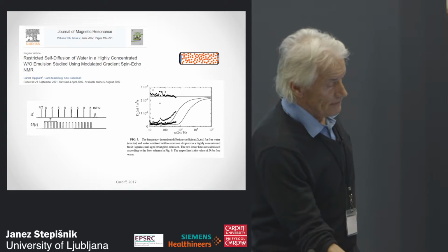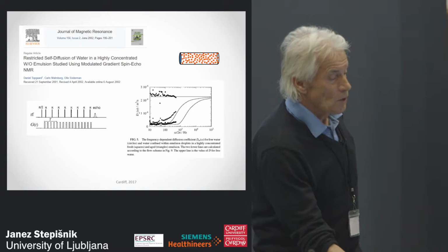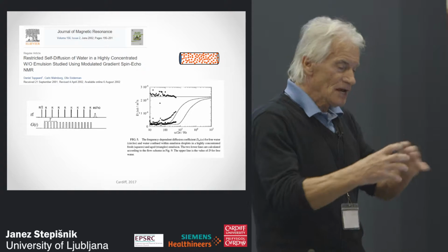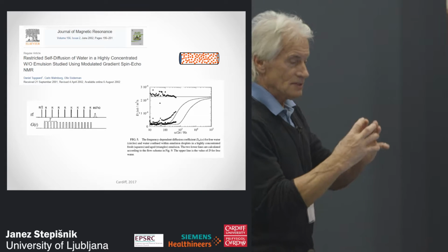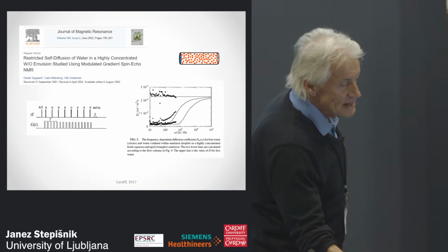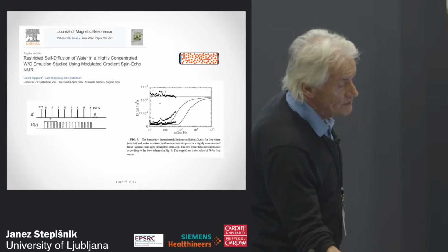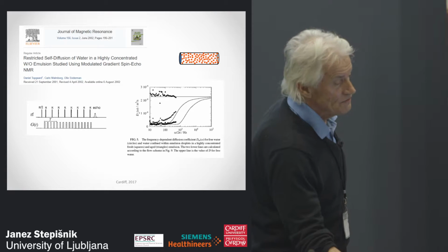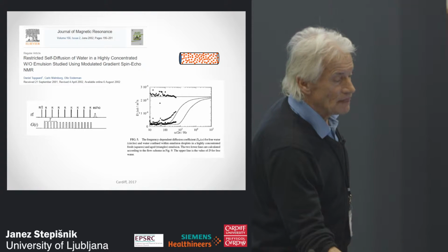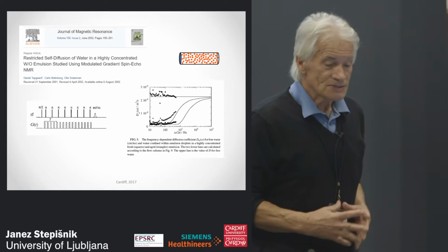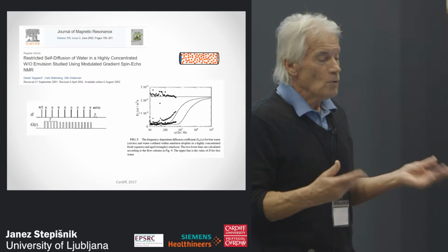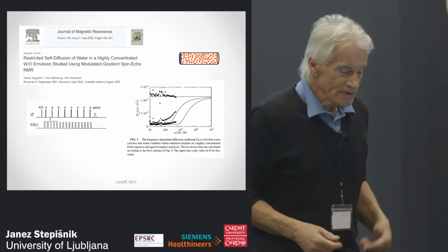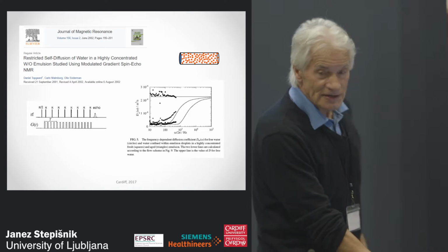And he says, this is a fresh emulsion where the droplets are pretty small, about a micron, and then after a certain time these droplets join and get bigger, and they get something. It is expected with such restricted diffusion. The only problem was with the frequency range. The frequency range was limited using such a sequence to below 1 kilohertz. Why? The inductance of the gradient coil, of course. We cannot switch gradient coils faster than that.